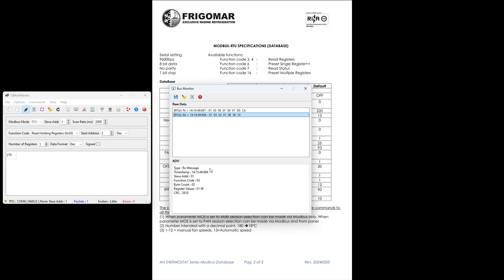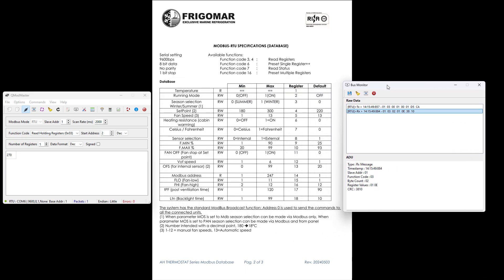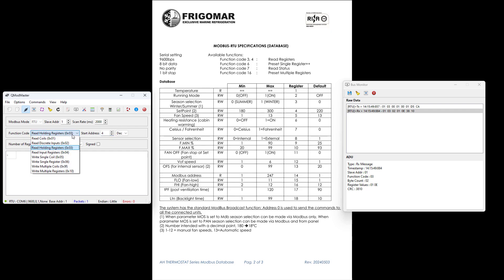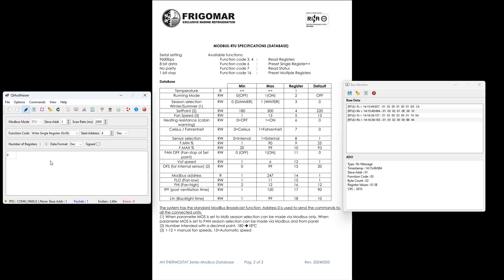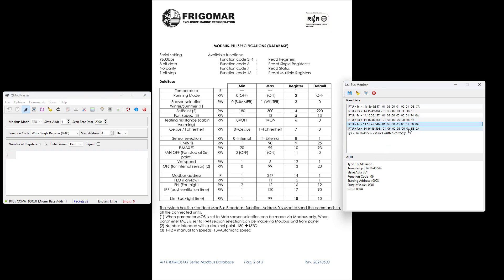As another example, let's try writing to a register. We'll use function code 6, write single register. Suppose we want to write to register 3, which in the documentation represents winter mode. Because of the offset, we'll enter 4 as the start address. After sending the command, we can see that the write completed successfully. It's useful to keep a record of these commands, because we'll reuse them in SIMPL Windows when working with a Crestron processor.